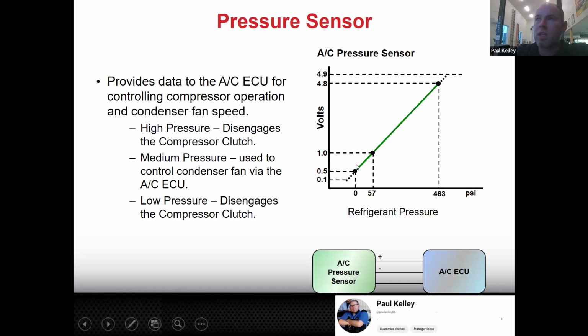Does that make sense? So they give you this range - it should be between a half a volt, and actually this one goes up a little higher than 4.5, all the way to 4.8. Half a volt to 4.8 is legit, those are real numbers. However, if it's below a half or above 4.8, there's a problem in the circuit, and it's going to set a code, a DTC.